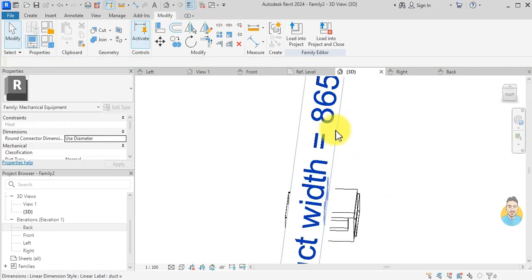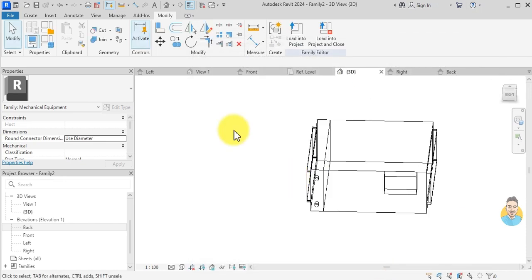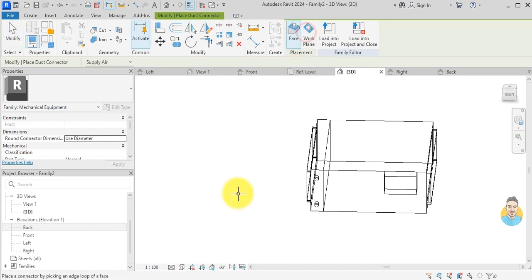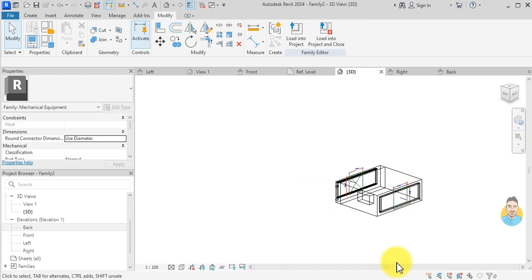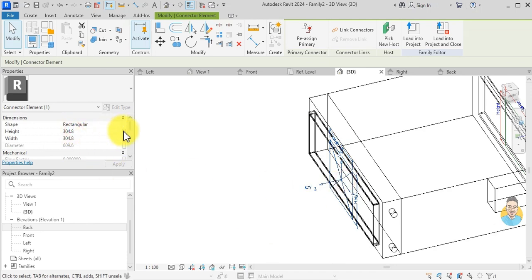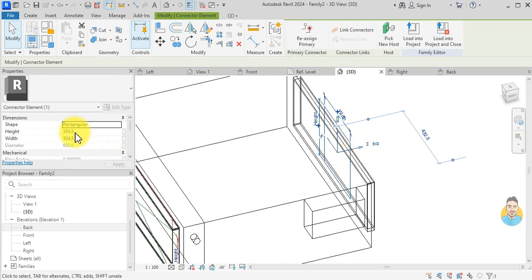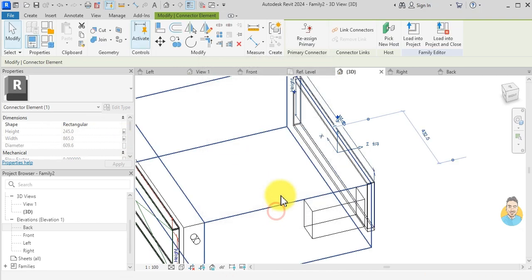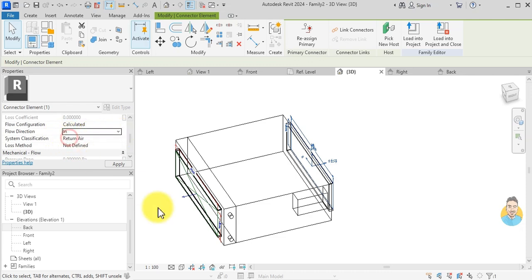I press VV and uncheck Annotation to hide annotation symbols. Now I'll add duct connectors. I go to Create Duct Connector and click on the supply duct opening and the return duct opening. I click on the supply duct connector and set the height to Duct Height and width to Duct Width, with flow direction Out for supply air. For the return connector I set height to Duct Height, width to Duct Width, type as Return Air, and flow direction In.